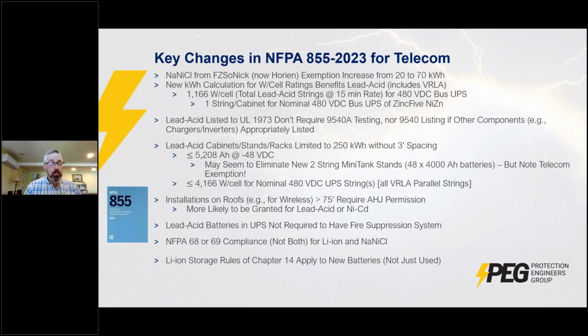Even UPSs and traditional telecom 48 volt plants have to comply with the code when they're over 70 kilowatt hours for a traditional telecom 48 volt plant, or 1166 watts per cell for a UPS type plant. And if it was a ZincFive nickel-zinc plant, that would be a one string plant that would fit underneath, and maybe the code would not apply to it.